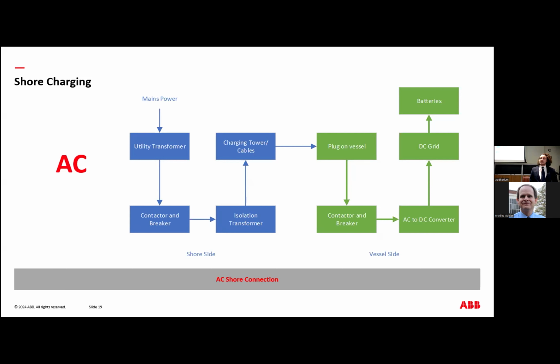Then you typically have an isolation transformer, either on shore or on the vessel, for galvanic isolation. Then the charging system, which can be cables handled manually, or for a ferry making 15 to 20, 30 connections a day, an automated robotic connection system. Then you have a plug or socket on the vessel, another contactor and breaker on the vessel to prevent backfeeding power and faults in that direction, and then the AC to DC converter, the onboard DC grid, and the batteries being charged.